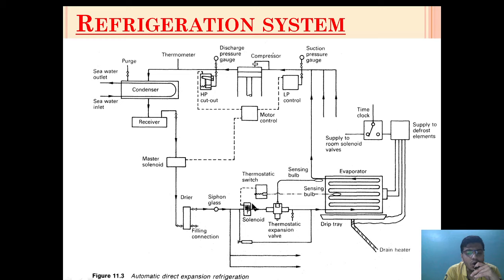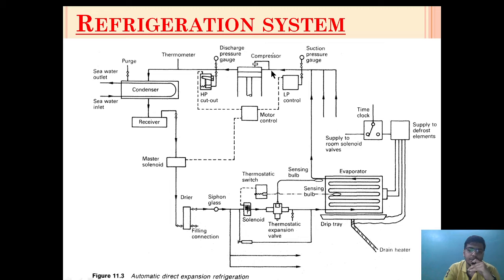Through the sight glass, the refrigerant will pass through a thermostatic expansion valve, which converts it from a high pressure liquid refrigerant to a low pressure liquid refrigerant. As it enters the evaporator, it will extract the heat from the refrigerated area, and as it boils off, it will convert into gas form and go again to the compressor suction.